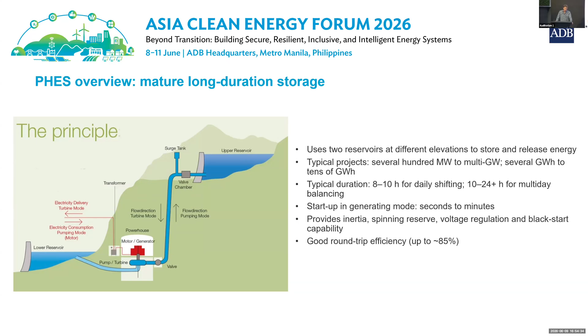Some strengths and limitations of this system: it's a very long asset life, we're talking about 100 years. Now Snowy 2.0 has proven 150 years, so we're designing for that life cycle. Large scale, long duration, no storage degradation - this will be compared with batteries. And the OPEX is really, really low, it's 1.5 to 2% of the CAPEX per year, giving a really stable storage system.